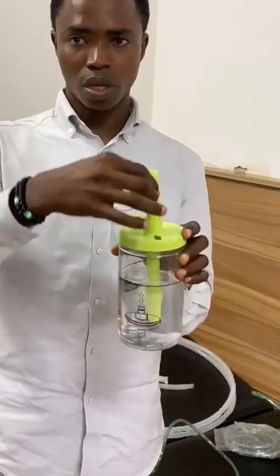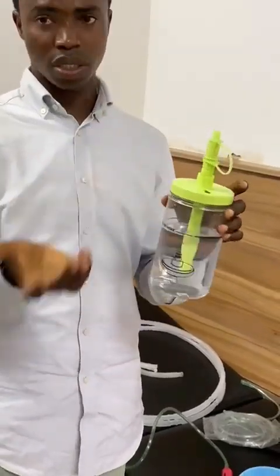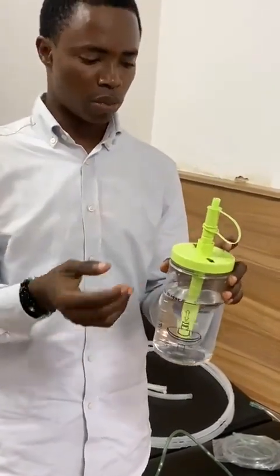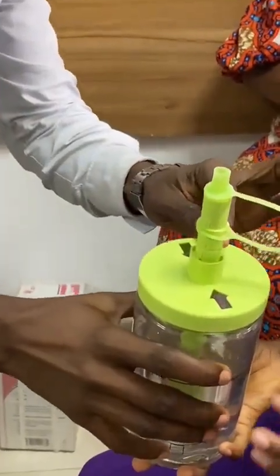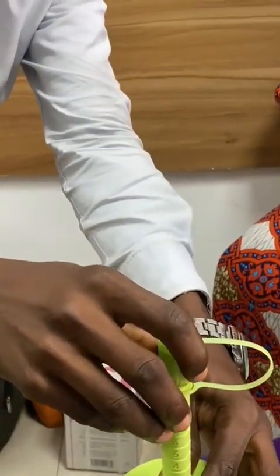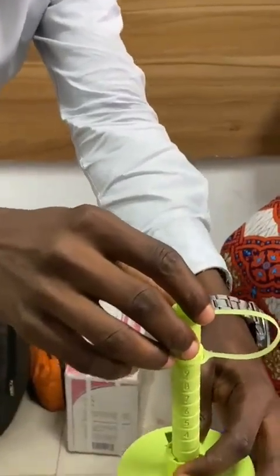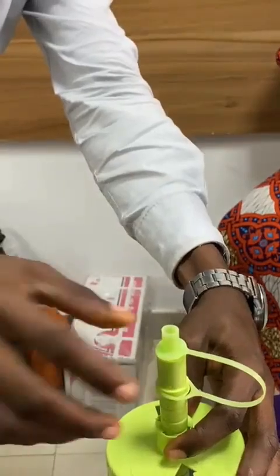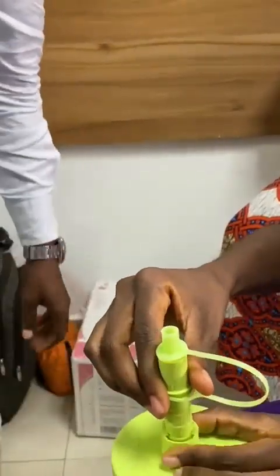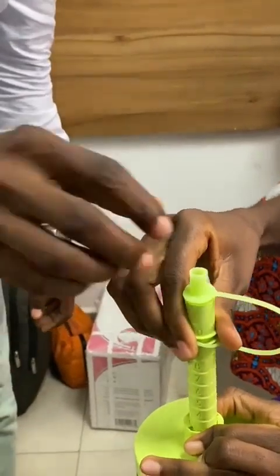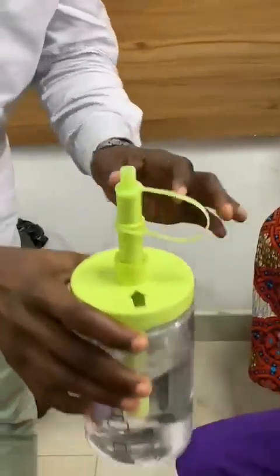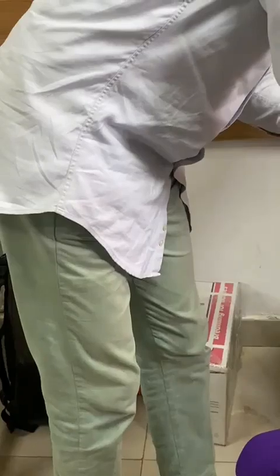To adjust your pressure under water, you may want to go to 6 centimeters of water, depending on the patient's requirements. There's a simple mechanism. Let me show you. You can see these two parts. It prevents the tube, which is a straight tube system, from falling or moving easily. So what you do is just pinch. Once you pinch a bit, you can easily adjust and push. There's a hook that is holding it. You can easily move it, but as soon as you leave it, it stays.